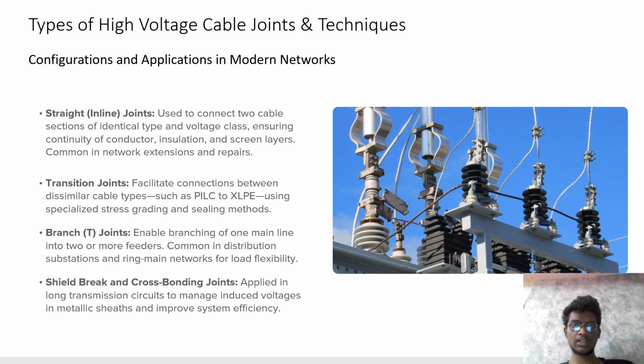Types of high voltage cable joints and techniques. Configuration and application in modern networks. Straight inline joints are used to connect two cable sections of identical type and voltage class, ensuring continuity of conductor, insulation, and screen layers, common in network extension and repairs. Transition joints facilitate connection between dissimilar cable types such as PILC to XLPE using specialized stress grading and sealing methods. Branch T joints enable branching of one main line to two or more feeders, common in distribution substations and ring main networks for load flexibility. Shield break and cross bonding joints are applied in long transmission circuits to manage induced voltage in the metallic sheath and improve system efficiency.